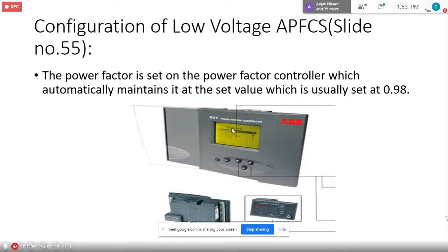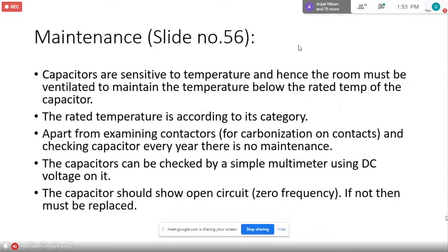Maintenance. Capacitors are sensitive to temperature, and hence the room must be ventilated to maintain the temperature below the rated temperature of the capacitor. Remember the category? Whatever the category, if it's a 40, then the room temperature must be below 40, say around 35. Apart from examining contactors for carbonization of contacts and checking capacitors every year, there is no maintenance. The capacitor can be checked by a simple multimeter using DC voltage on it. The capacitor should show open circuit, zero frequency. If not, then it must be replaced. Very simple, straightforward.